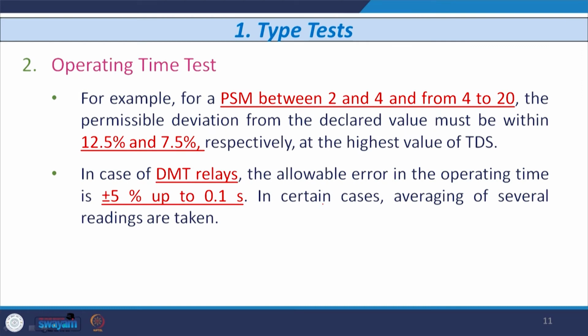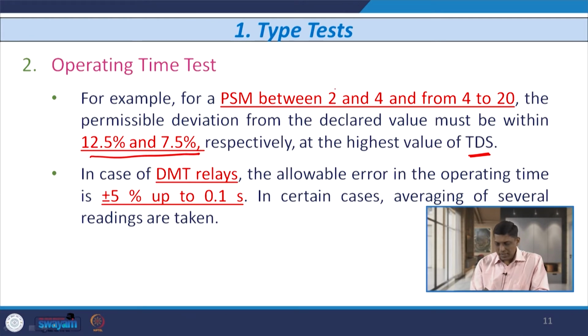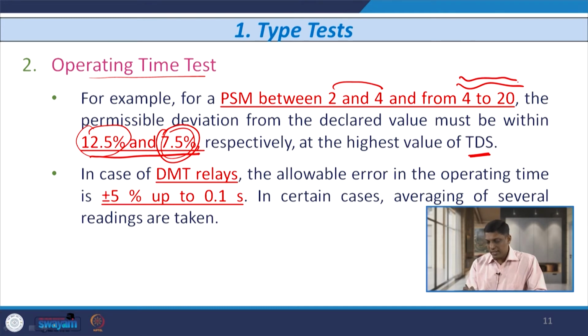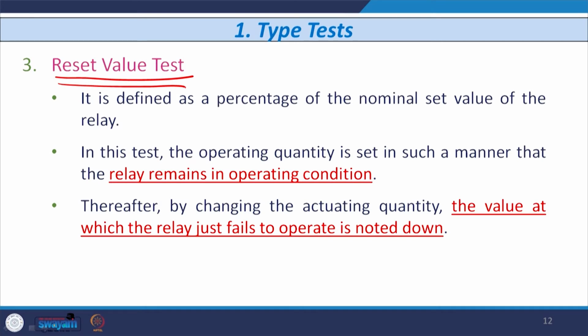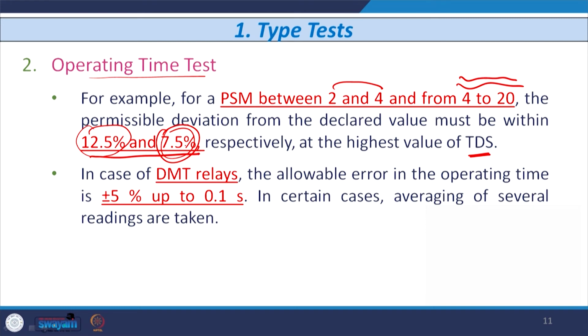Now, when we consider the operating time, for example, for the plug setting multiplier between 2 to 4 and from 4 to 20, the permissible deviation in the operating time may be 12.5% and 7.5% at the highest value of TDS. So, for the PSM between 2 to 4, the allowable range for the operating time test is 12.5%, and for 4 to 20, the allowable range is 7.5%. If I vary the PSM between 2 to 4, the variation in operating time should be 12.5% with reference to the nominal value. Similarly, if I vary the PSM between 4 to 20, then the allowable variation in the operating time should be 7.5% of the nominal value.